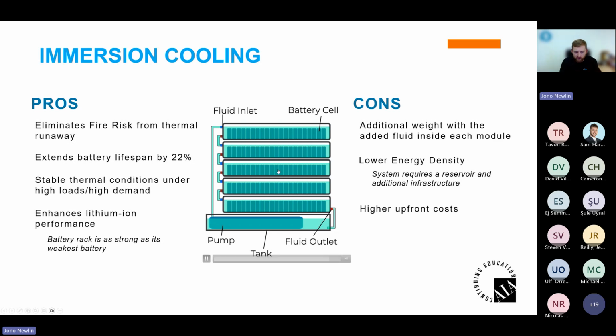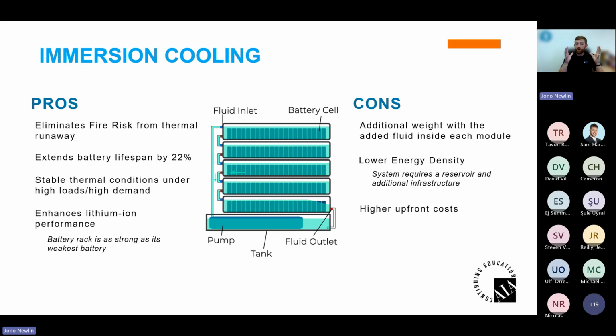So what immersion cooling does is, yes, it is the primary coolant mechanism for the battery cells, but additionally, it's always in place. As you see here, say a center rack, center cell goes into thermal runaway. What happens in an immersion cooling system? Well, that cell goes into thermal runaway. We can never stop a thermal runaway if it's an internal breakdown of the cell. Could be a quality issue, whatever it might be. But it does propagate heat, and that heat is absorbed through the liquid. So it doesn't transfer directly into those neighboring cells the way it would without the liquid present. So this actually eliminates the thermal runaway propagation and the fire risk.